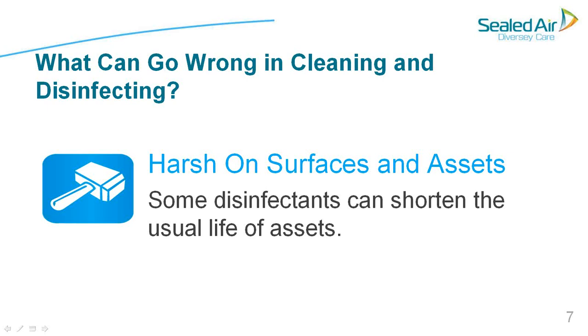Even within the approved list of chemicals that you will find from manufacturers that make medical devices and patient care equipment, you will often find chemistries listed that are known to damage the surfaces. But because of their presence in the market, meaning these products are sold very widely, they're often included so that customers have some measure of comfort in use of the product. This then creates situations where even products that are recommended can exhibit some degree of risk.